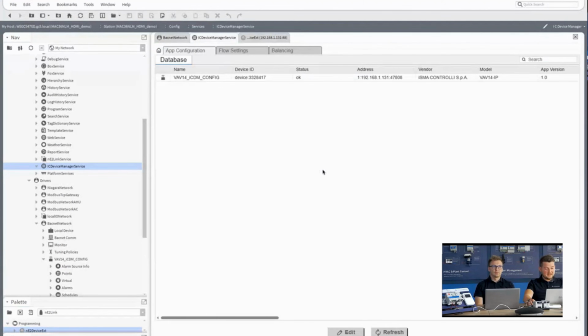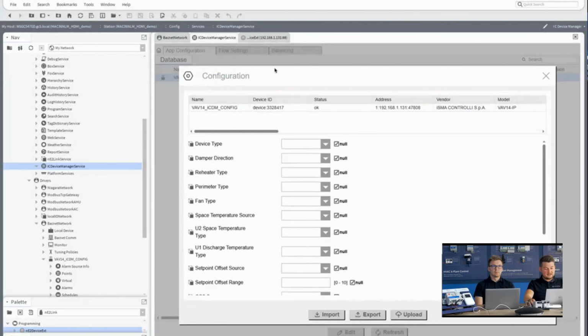Now we can open the VAV, and as I can see, I have the same unit I had on my BACnet network. It pops up automatically based on the model. So if you have 100 of them, you'll see 100 of the VAV devices right here. And as you can see, I can access the same configuration I saw in the iSMA Configurator and do similar configuration directly from the tool.